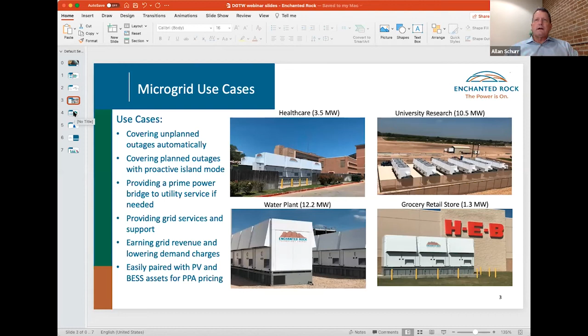Let me give an example where all of this comes together. As so many people know, during the Texas winter storm this year, Winter Storm Uri, the grid struggled because of extreme weather in maintaining supply and demand. There were large central station power plants that were shut in—they weren't winterized properly. Fuel was not available to all locations, and loads were at record levels. The cold was intense, to be sure, but there was also significant migration over the last few decades to more electric heating in Texas. Electric heating during very cold weather suddenly shoots up in kW demand draw as resistance heaters kick in below certain temperatures.